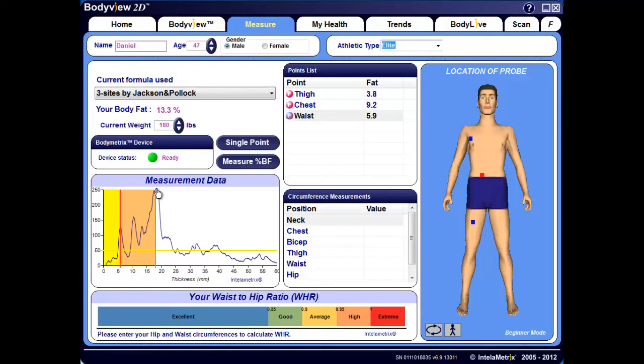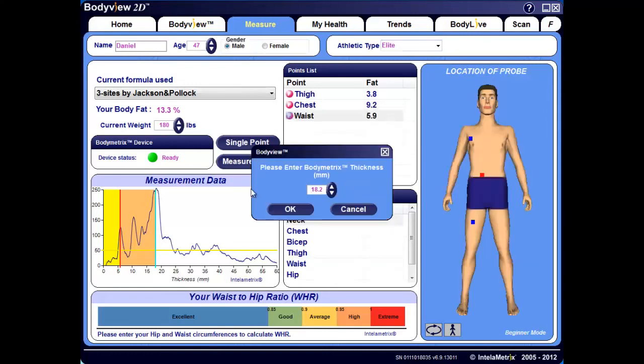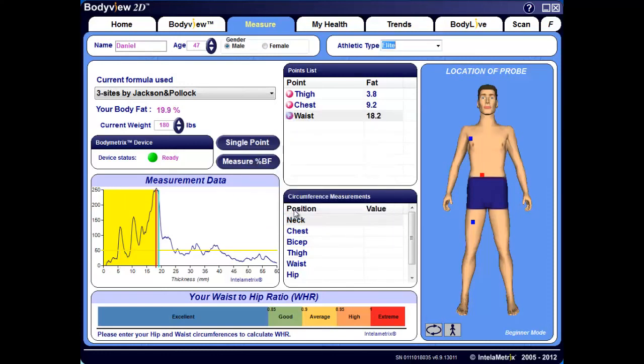The importance of analyzing your measurement data graph is critical to ensure accurate measurement readings in the waist. Consider one scenario where you set the athletic type to elite and the software chose the first peak at 6 millimeters after taking your measurements. Using your reference of 25 millimeters, we know that 6 millimeters is less than a third of an inch of fat, but for this individual it's obvious that they have a noticeable fold in the waist, so the most likely characteristic peak is in fact the strong peak at 18 millimeters. Knowing this, you can manually override the automatic peak detection by clicking on the peak at 18 millimeters and accepting the change by clicking OK, which forces the software to use this peak as the true fat-muscle interface.